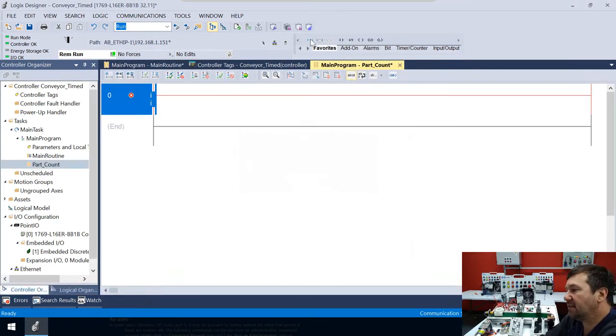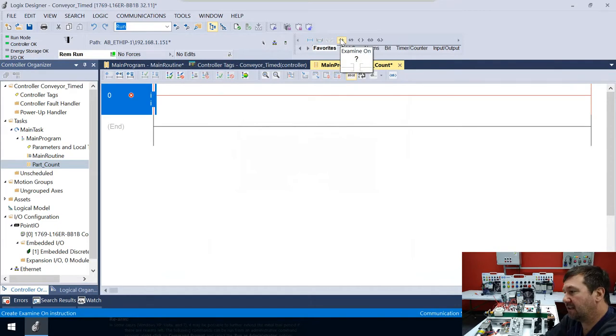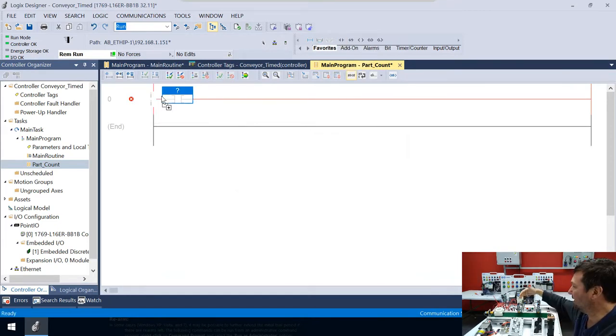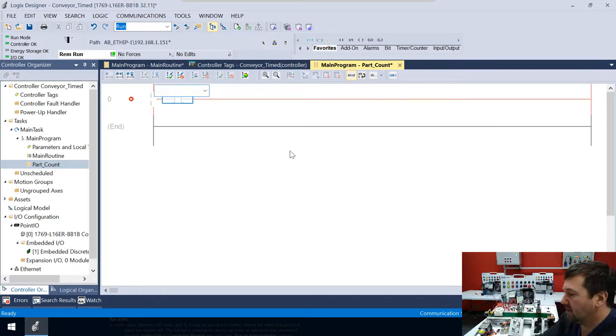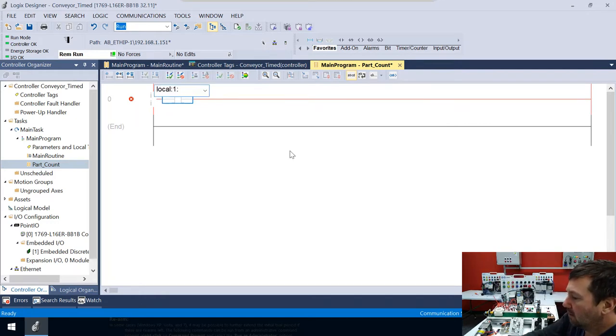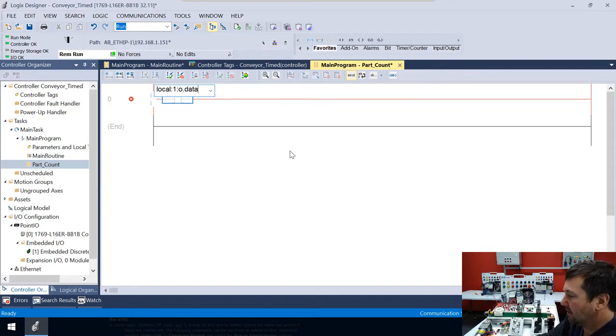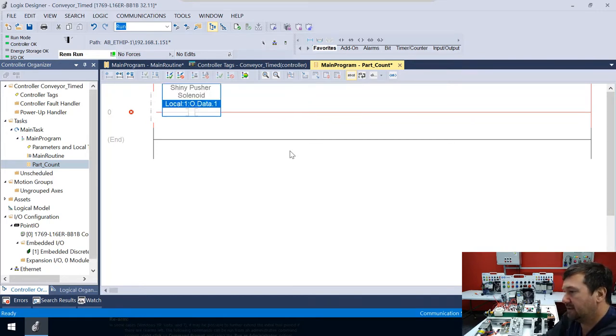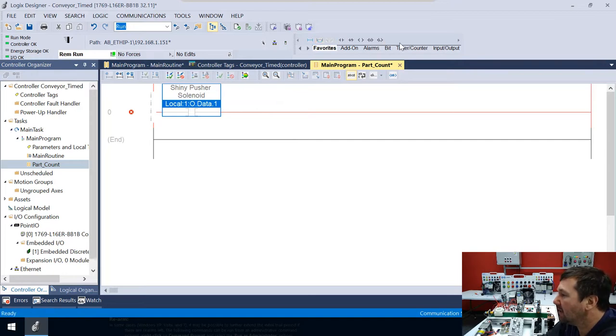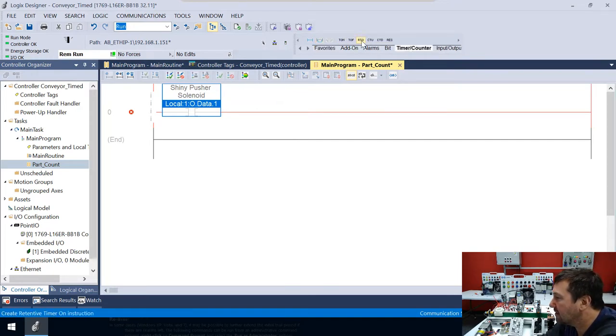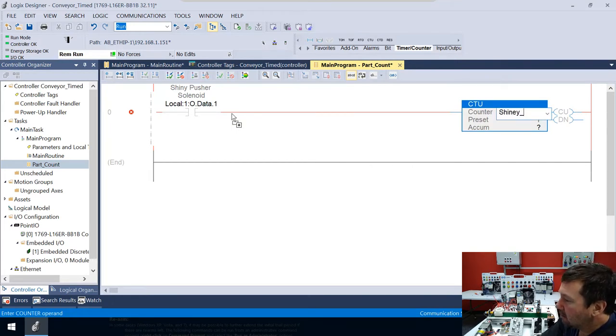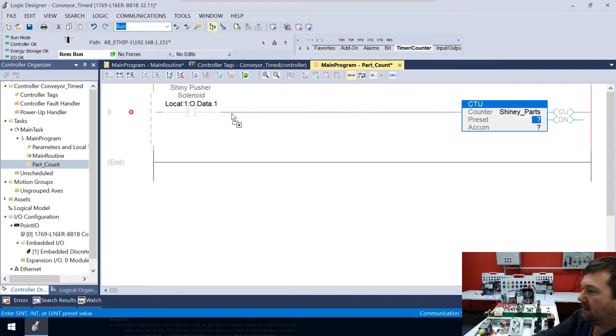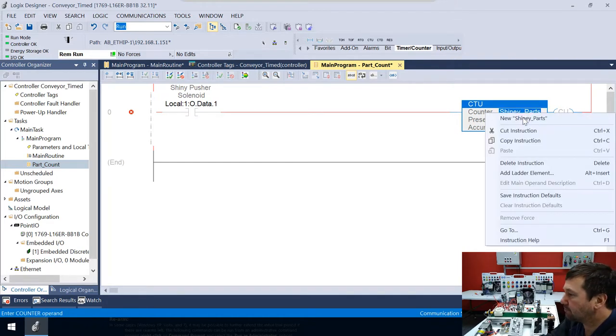So in this case, what I want to do is I want to examine on, and anytime that I see this ejector go out, I want to count the part. So that is going to be local colon one colon O dot data dot one. So that's our shiny pusher solenoid. And then we're going to bring down a CTU count up counter, and this will be shiny parts. So we'll need to create that.